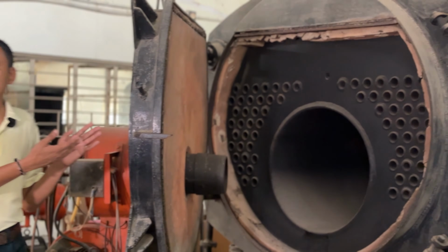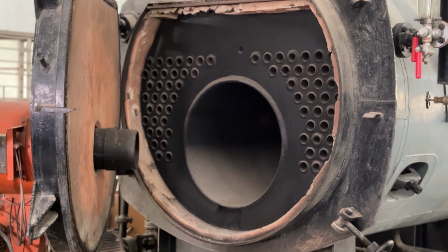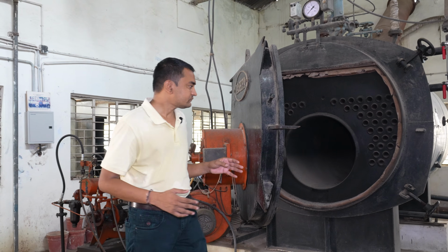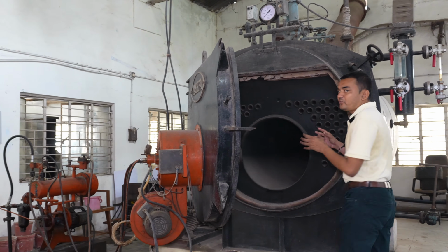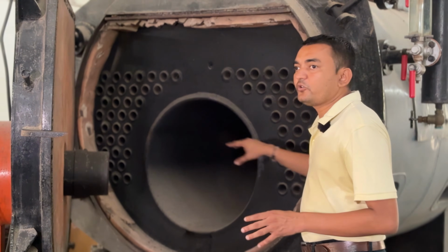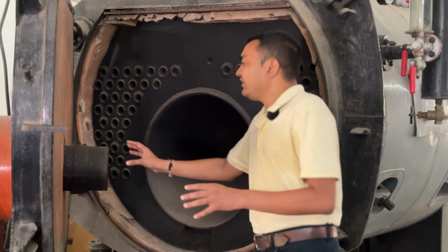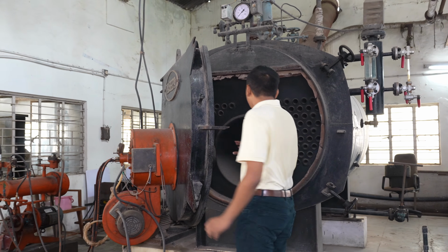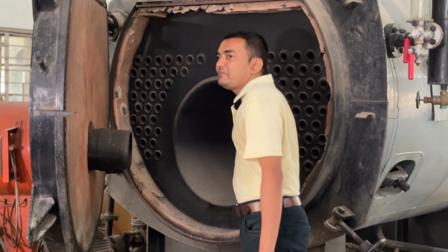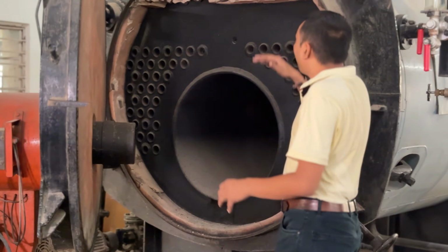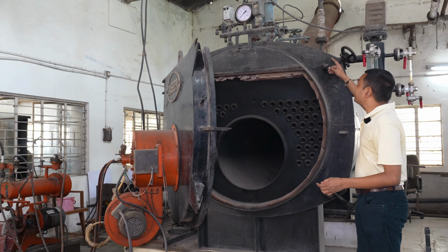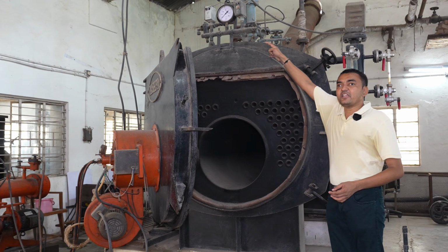Now you can see the Lakshmi package boiler, a fire tube boiler, over here. I want to explain to you the various parts and working of this boiler. You can see the tubes: one big tube and other small tubes. Firing takes place with the help of diesel firing, combustion takes place over here and flue gas is produced, which goes inside the big tube and then comes into the small tubes. Water is in contact with these flue gases and is converted into steam. That steam is carried through the steam stop valve to the steam engines.